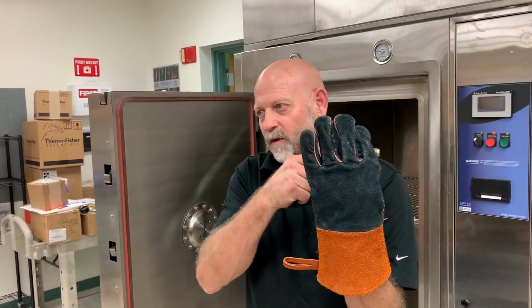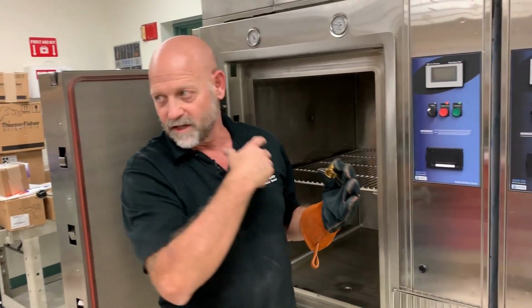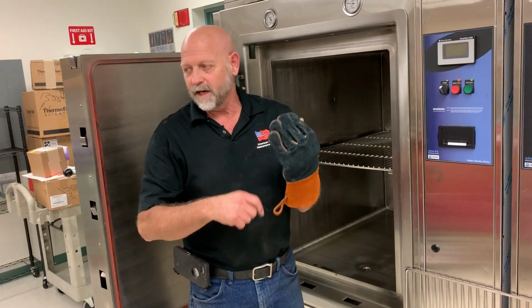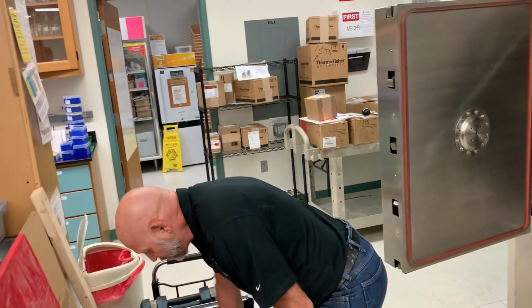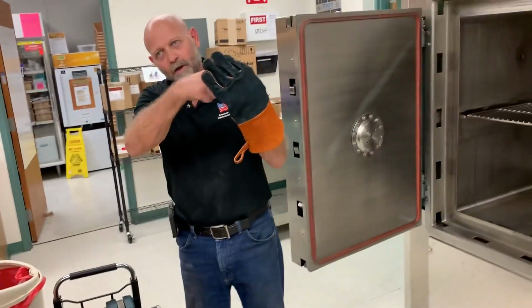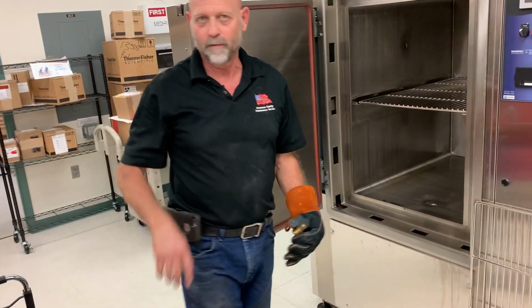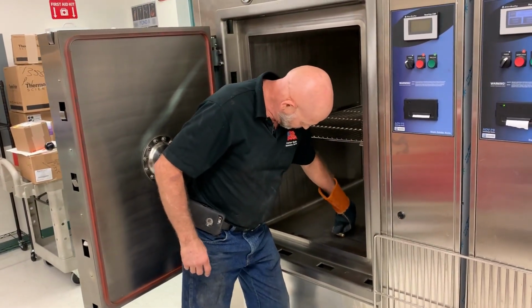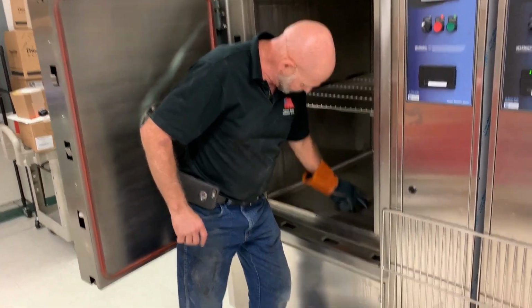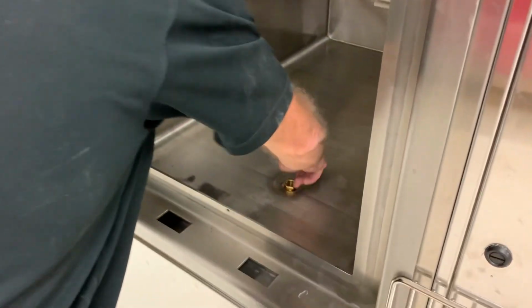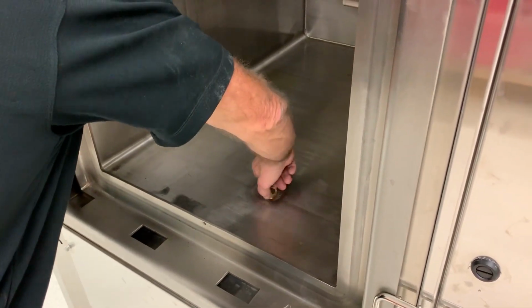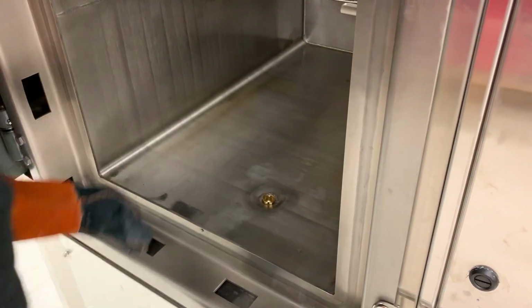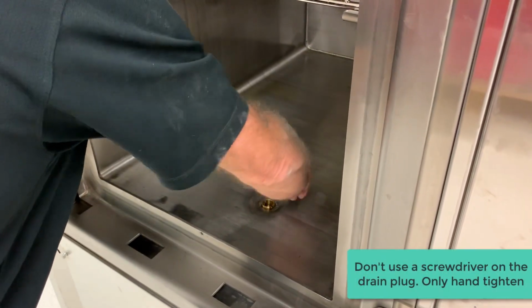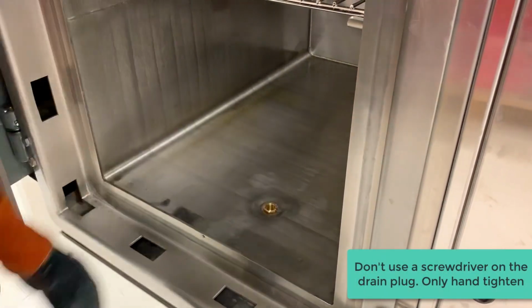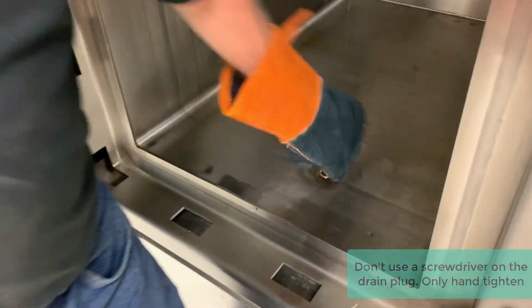If this fills up with garbage, the sterilizer won't reach temperature. So you just clean it out. Sometimes I use a little brush that goes inside there. You can pick it up at Lowe's. Okay, we're going to put this back in, and you just want to go finger tight. Like I said, you don't want to tighten it with a screwdriver. The slots in it are not for a screwdriver. The slots are to let liquid in.